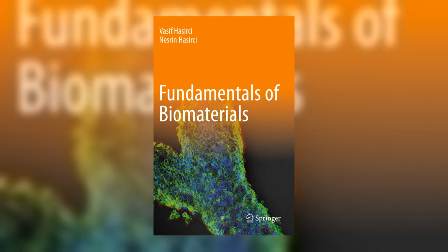This part explains why ethylene oxide sterilization leaves a residue you have to remove. The same reactivity that sterilizes is the one you must then evict. Ethylene oxide kills by alkylation. It attacks the membrane, then the DNA, and the attack is blind to whether the cell is a contaminating microbe or the patient's own tissue. The gas that clears the device does not distinguish targets. What it did to the pathogen, it will do to the host.